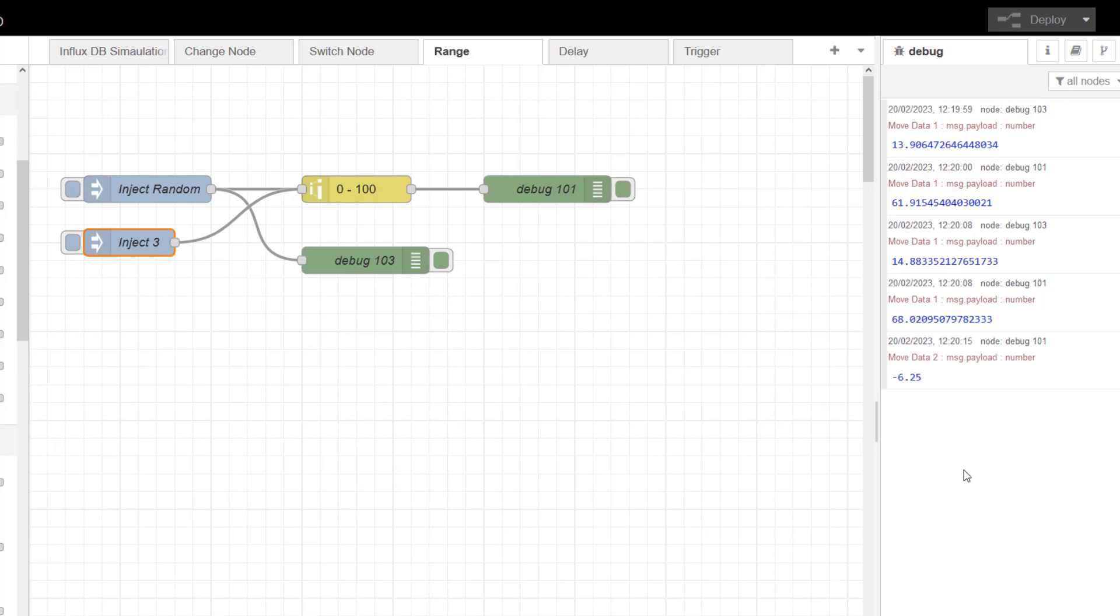And like I say, that could just be... it's a bit of a big jump, 1mA to be honest, it's probably going into a fail safe condition. But if it was 3.9 something, I think it could be that you've got some resistance in the cable that's just stopping that signal going to where it needs to go.